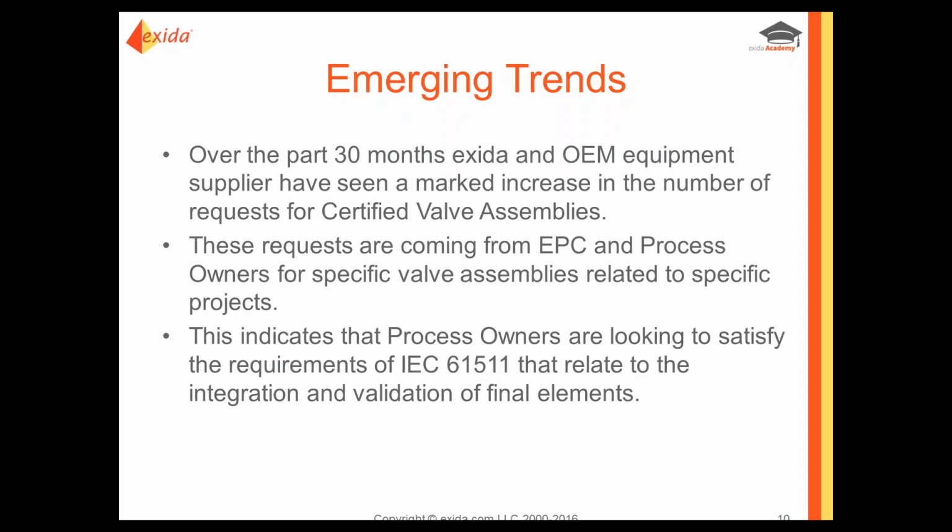So it might seem like overkill. It might seem like, is that really necessary if you buy a certified valve and a certified actuator? But when we take a look at what actually goes into these final elements, I think we'll see that there can be quite a bit of complexity, and there is the requirement within 61511 to demonstrate that the equipment used in these safety systems will function correctly.